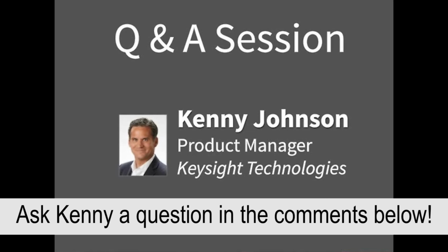For some of our higher performance probes, the performance verification procedure requires other equipment. We're talking about the really, really high gigahertz probes, where there are some other fixtures that you can buy that are necessary for these performance verification procedures. But that's the first thing I do, is just the user cal.